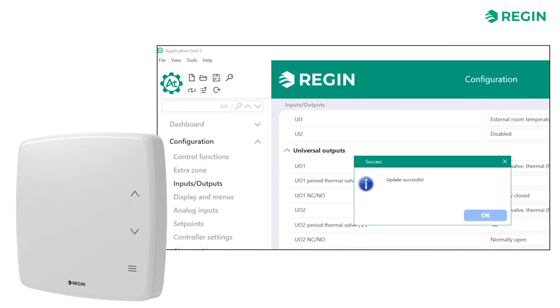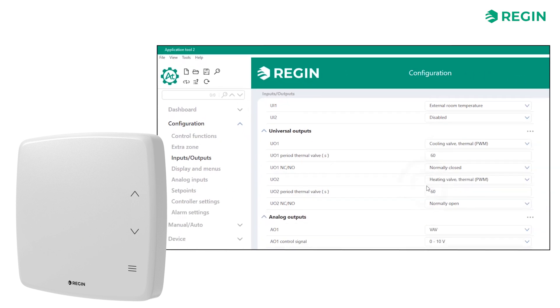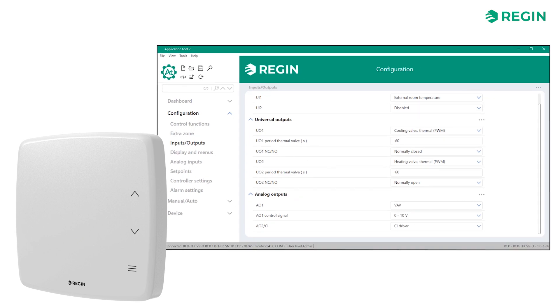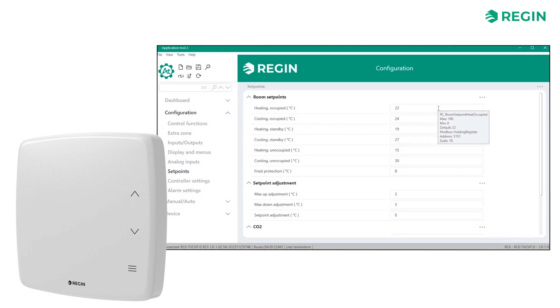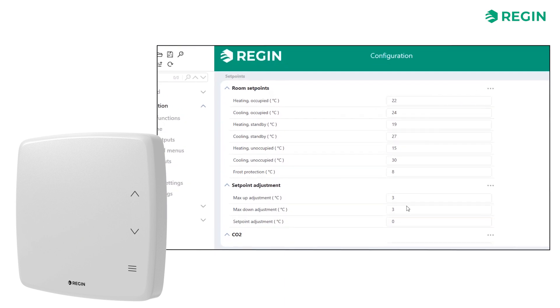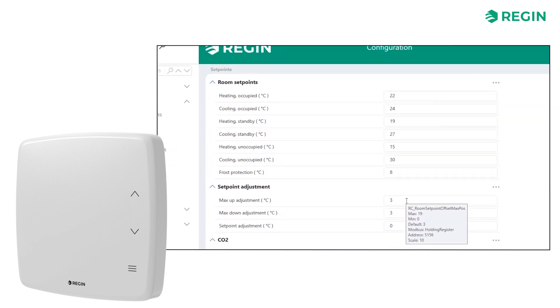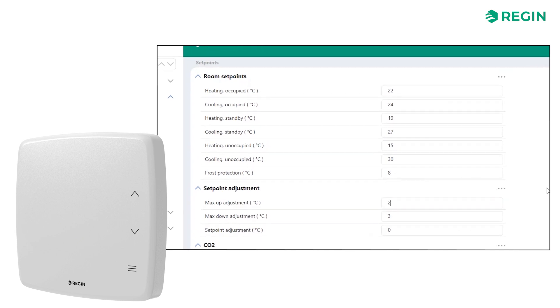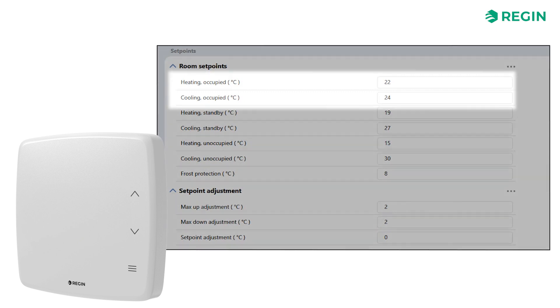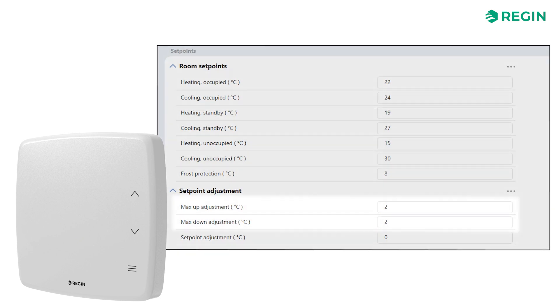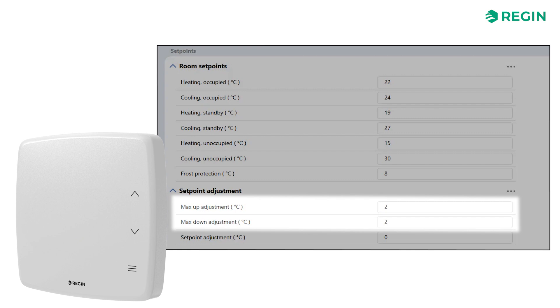With that, we have made enough configurations to let the Regin RCX function. However, there are more settings available if you want to fine-tune your configuration. On the Set Points page, for example, we can configure the different set points for Temperature, CO2, Humidity, etc., as well as how much adjustment is allowed when operating the controller via the onboard display. Here, we have set a heating set point of 22 and a cooling set point of 24, with an allowance of ±2 adjustment.